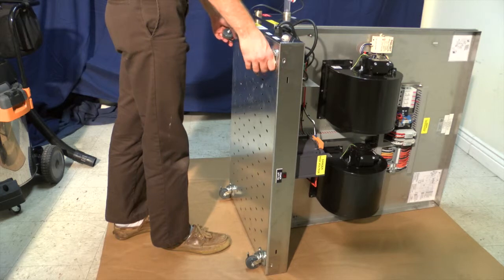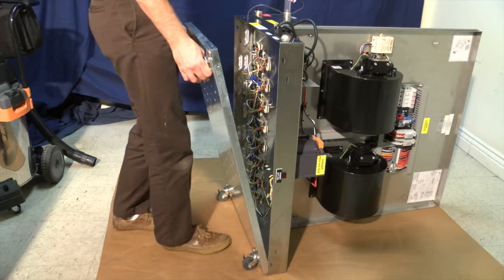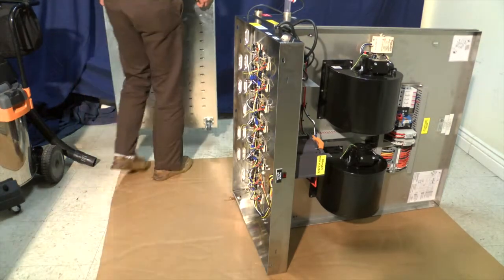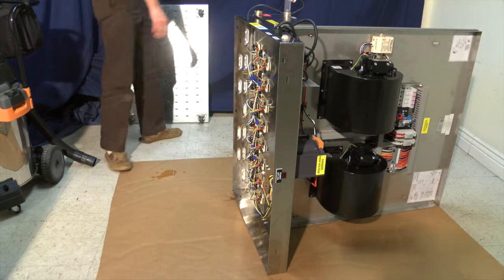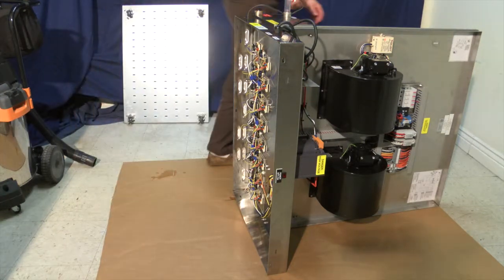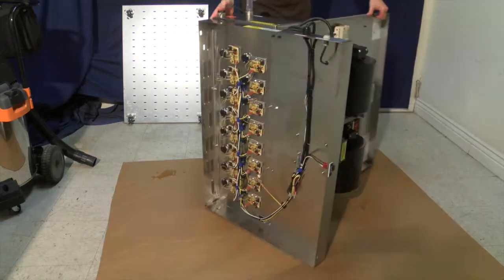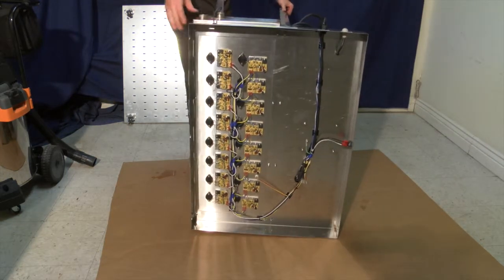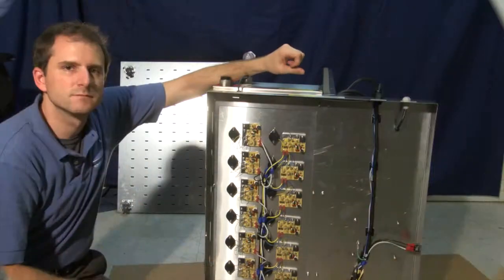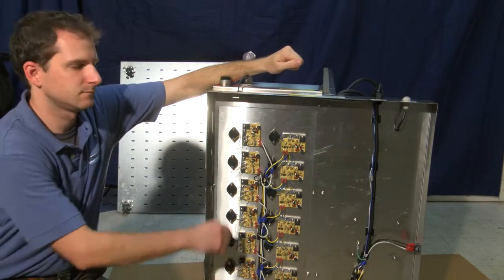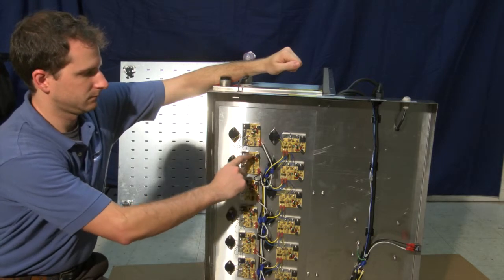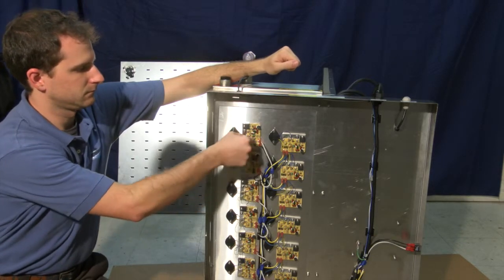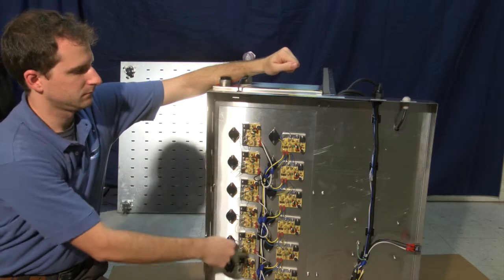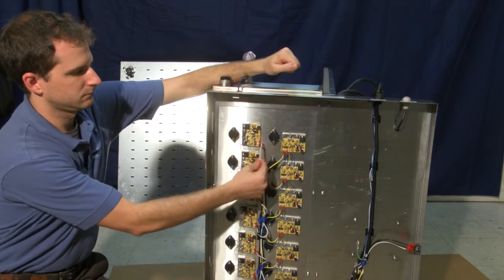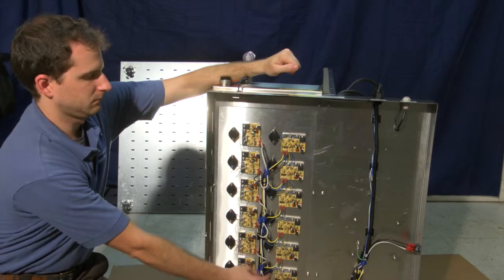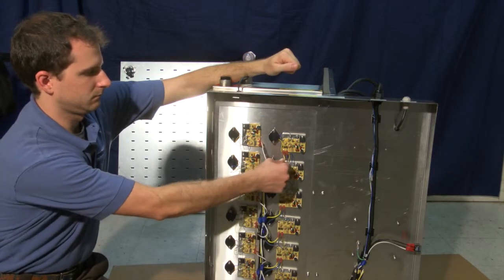You can then simply remove the unit's wheelbase. This will allow you access to the transducer bed. You can see each transducer has a corresponding circuit board that drives it. There will be a blue and yellow wire in between the circuit board and transducer. There is also a daisy chain harness that connects and powers all the circuit boards of the unit.